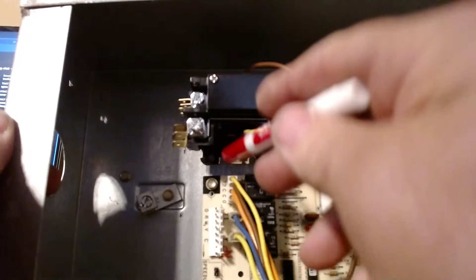So up here we have T2, common, common, O. All right. So our O and our common for the reversing valve are together. Down here, our defrost thermostat, and our dip switches for our defrost setting. See that this is your connection point between your high and low pressure switch. Low pressure, high pressure, right here. Here's the other ends. If I were to cut this off and take a continuity between this wire and these two blues and these two yellows, either it would go or not, because we don't have any pressure.